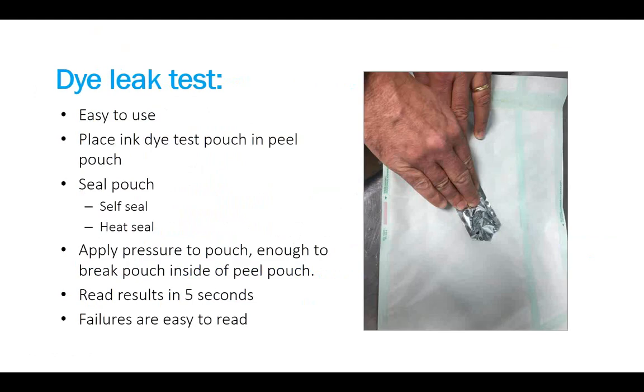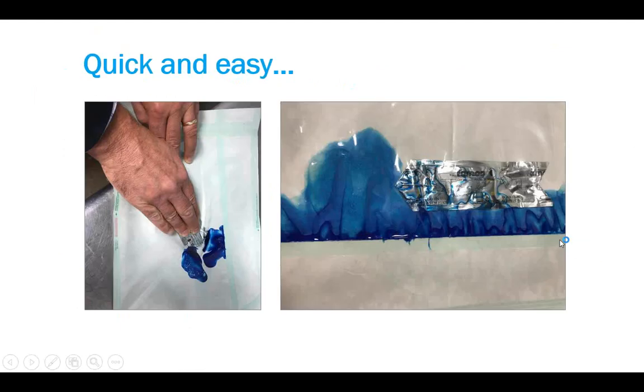It's easy to use: place the ink test pouch in the pouch before you seal it, whether it's self-seal or heat seal. You can see up here, I've got the heat seal. I'm sort of just making this test here. You apply pressure with your fingers on the pouch, enough to break the pouch, and you read the results in 5 seconds. The failures are easy to read, very easy to read.